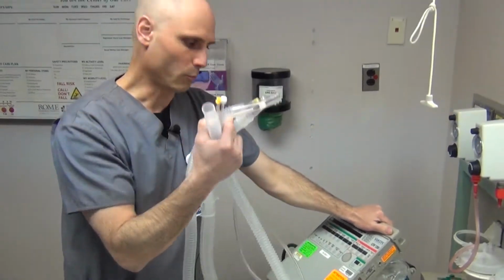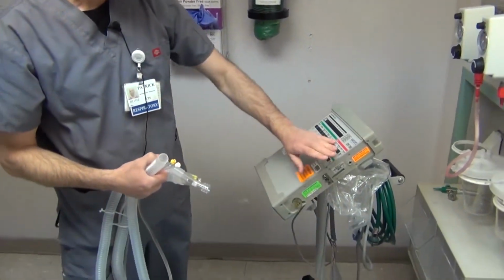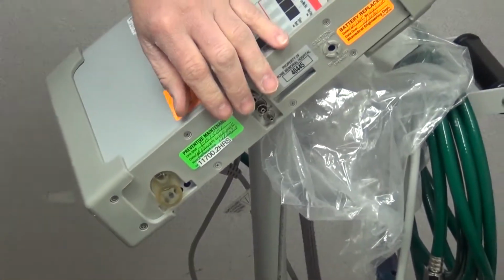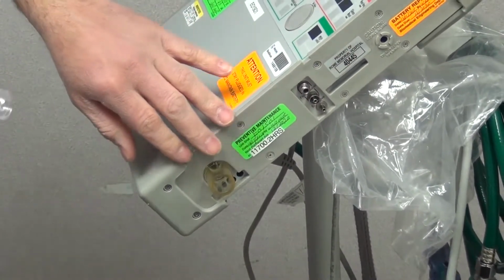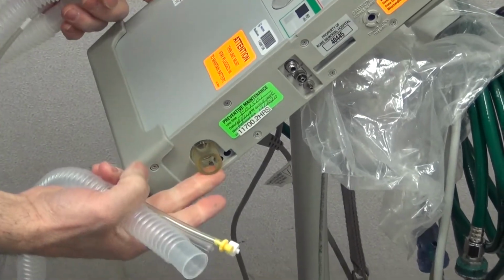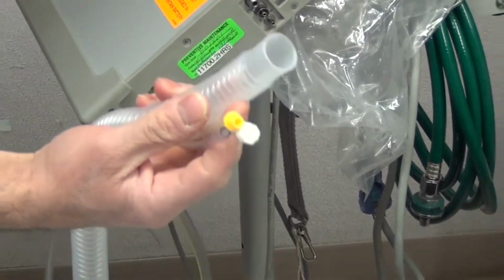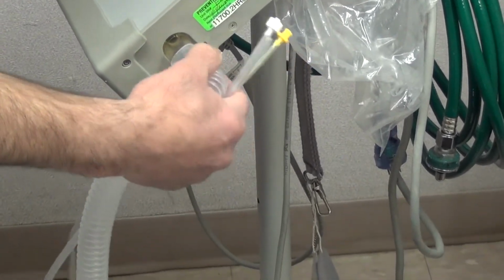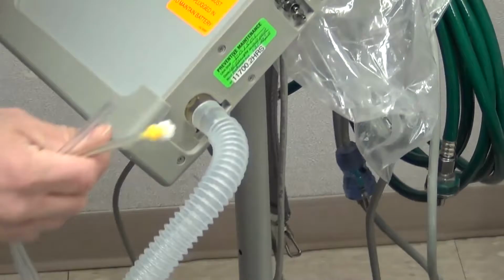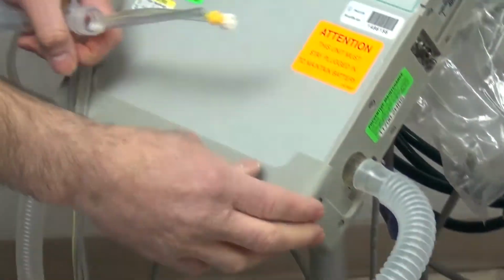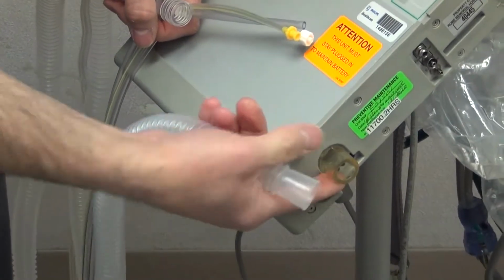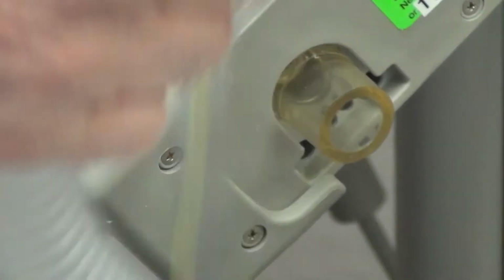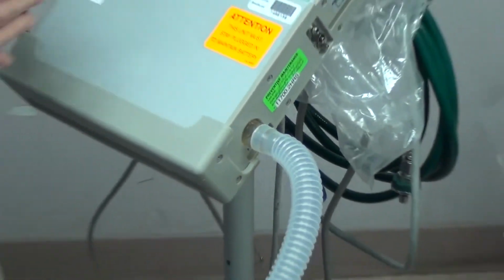There are all these little ports, and they're all located on this side of the ventilator, which, if you're facing the ventilator, will be on the right side. You notice the big port here? That is where this hose will plug in. And it is kind of hard to plug in. You have to stretch it over that. If you notice this little plastic piece is missing, look in the bag that you got this tubing from, the circuit, and you will find an extra one. Most of the time these are always plugged in, and they stay in pretty tight. So we plugged it back in.